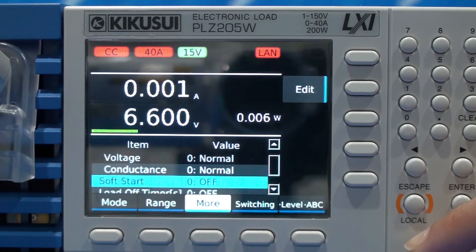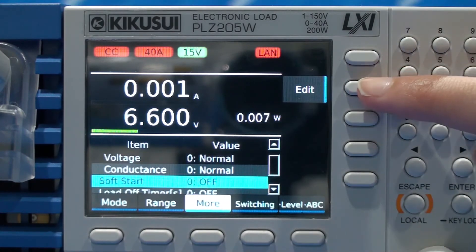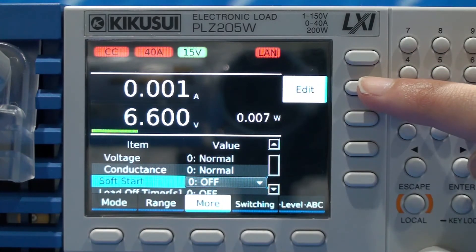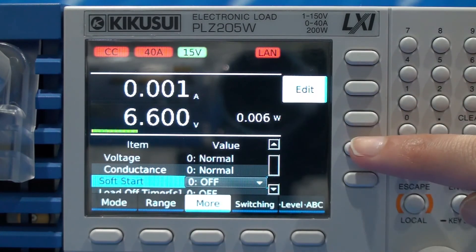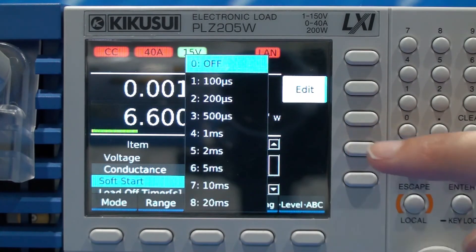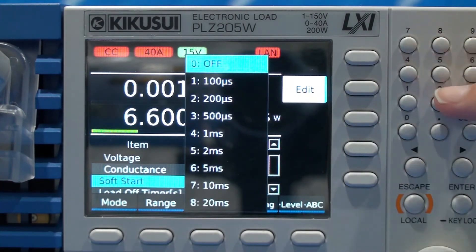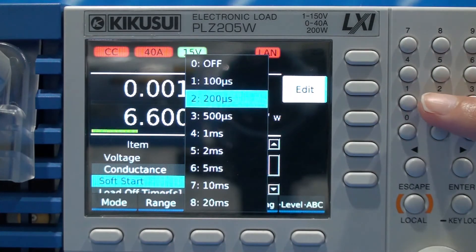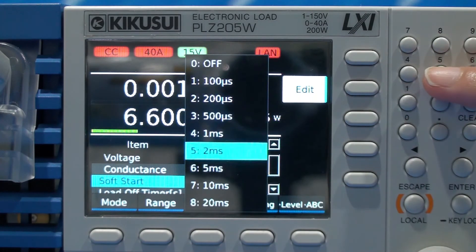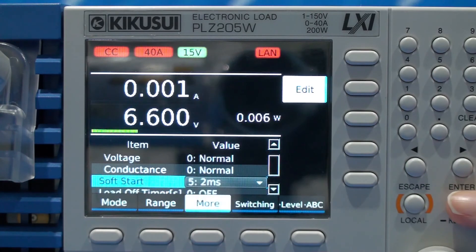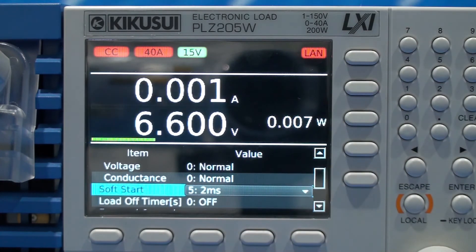Select edit and here you can activate the soft start function. You can select the time from 100 microseconds to 20 milliseconds. Let's set soft start for 2 milliseconds.